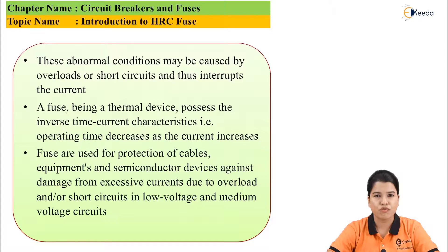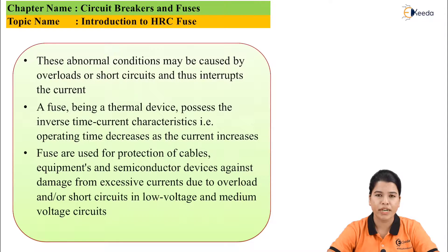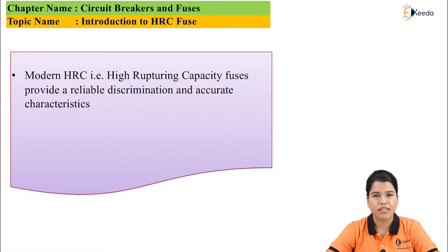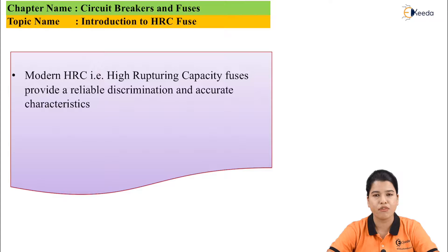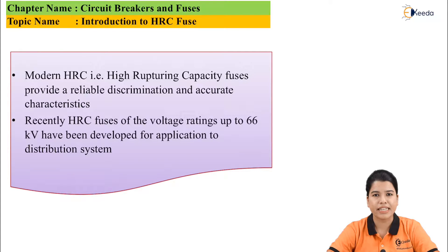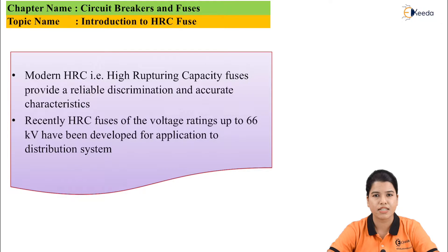The fuse is basically used for the protection of cables and various devices and equipment present in the power system from overload or short circuit conditions, but it is only operated for low voltage capacity. The modern HRC — that is, high rupturing capacity cartridge fuse — is used, which provides proper discrimination and isolation of the faulty system from the healthy system. Recently, HRC fuses have been designed for operating up to 66 kV.